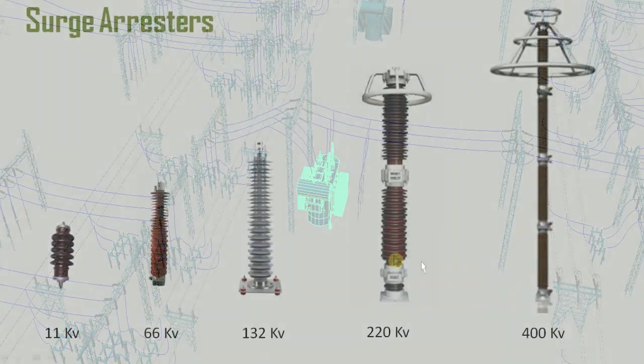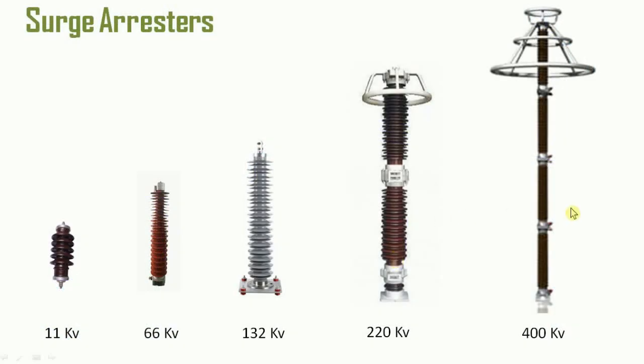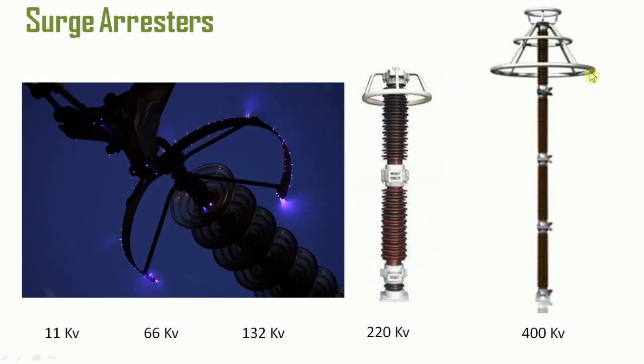As we discussed in the starting, what is the purpose of these rings? These are installed to prevent corona losses. Friends, in high voltage power substations, the problem of corona arises due to high electrical charge density over the surface of conductors, which tries to ionize the surrounding air and leads to generation of luminescence around conductors. The tendency of occurrence of this effect is more at joints and sharp points like terminals.